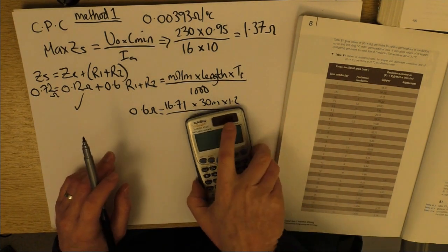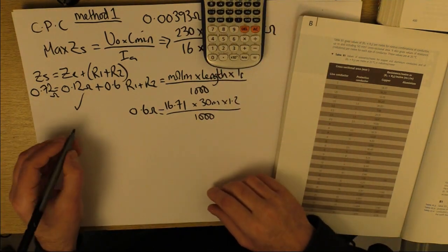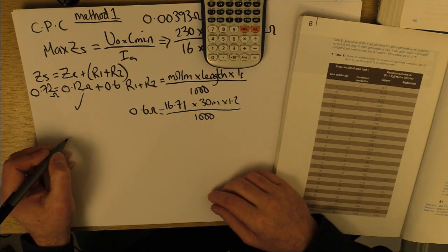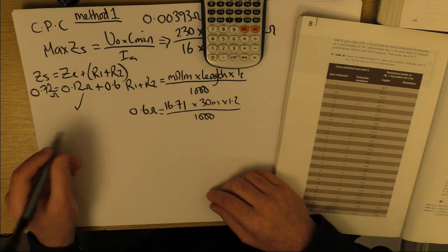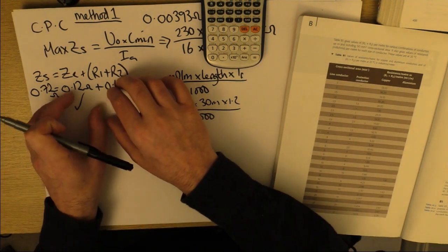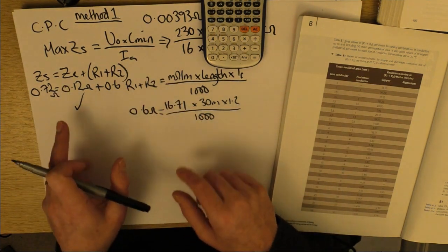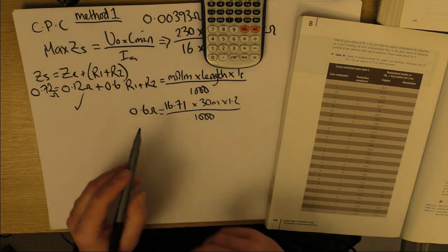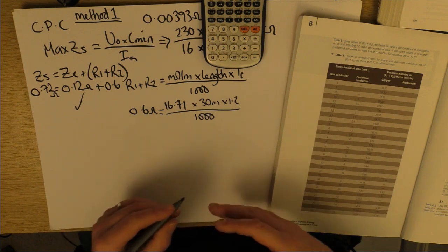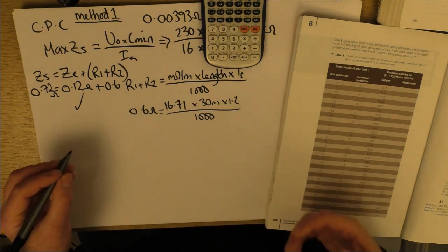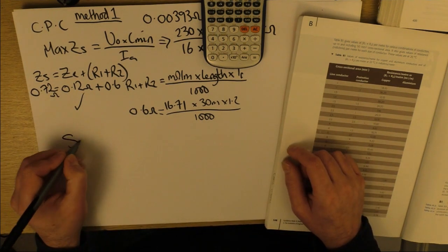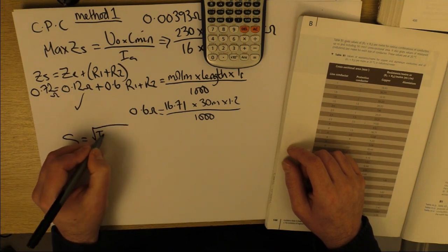And my hunch is that a 1mm² might struggle with the next bit, which is the adiabatic or the thermal constraints. So we know that it's going to generate enough fault current to trip the device, but can that C.P.C, the 1.5, sustain that fault current for that time until it disconnects? So that's where this adiabatic comes in.